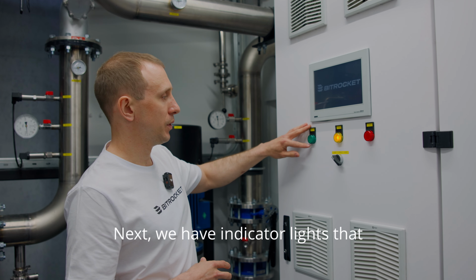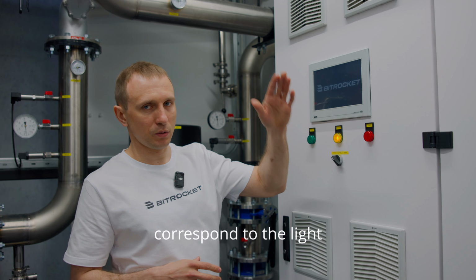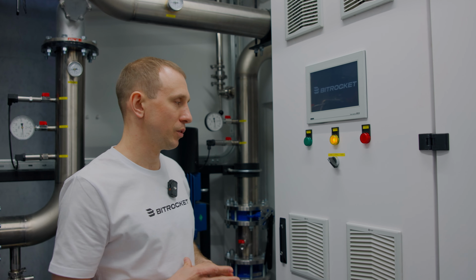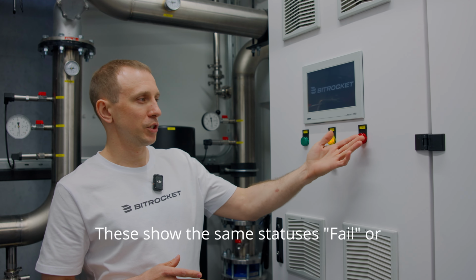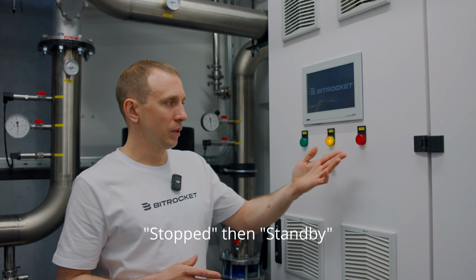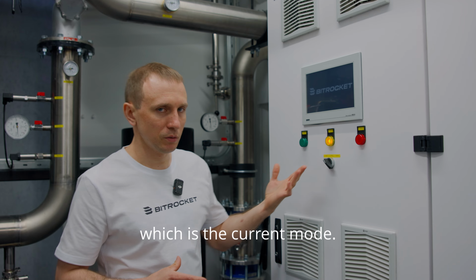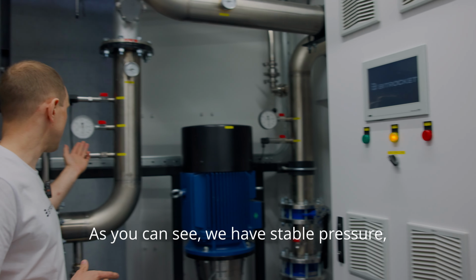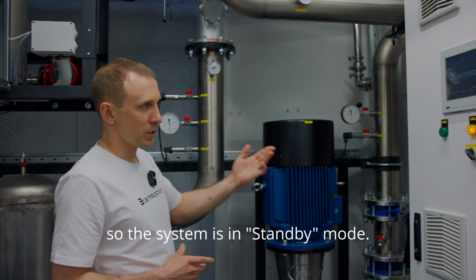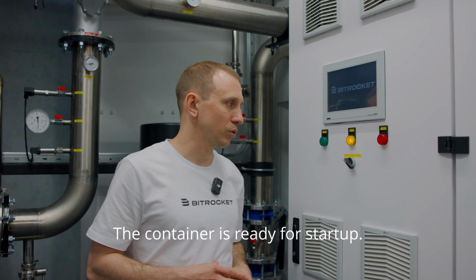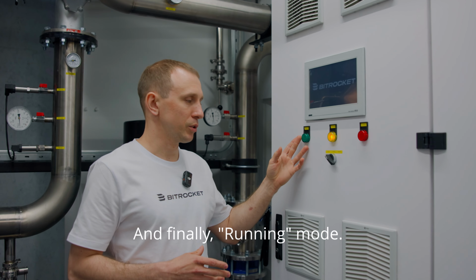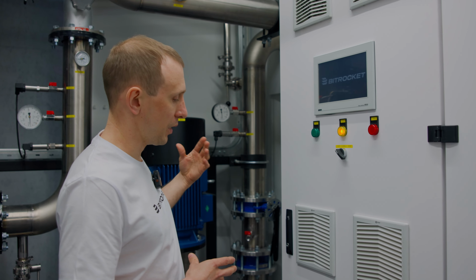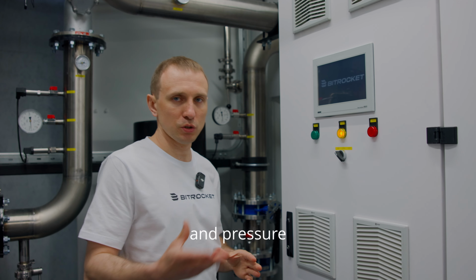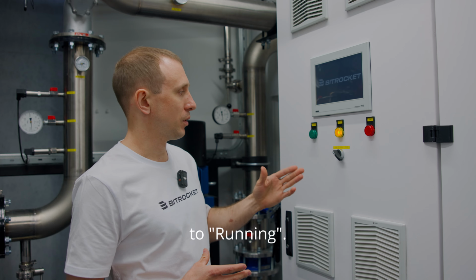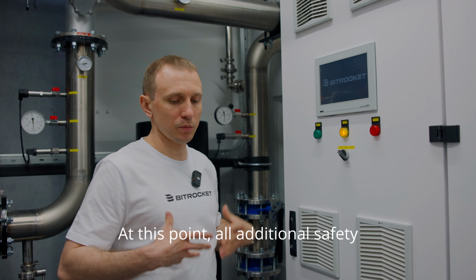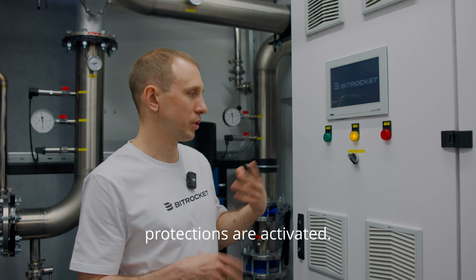Next, we have indicator lights that correspond to the light column you've already seen. These show the same statuses: fail or stopped, then standby, which is the current mode. As you can see, we have stable pressure, so the system is in standby mode. The container is ready for startup. And finally, running mode. When the pump reaches the required flow and pressure differential, the system switches to running. At this point, all additional safety protections are activated.